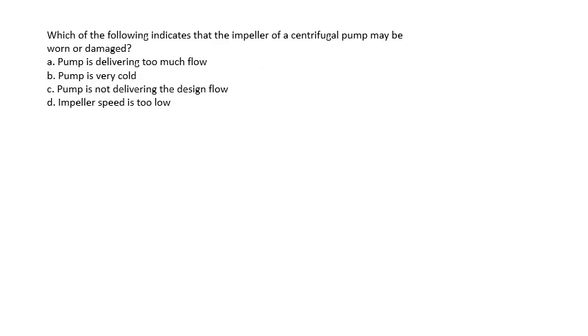Question 9: Which of the following indicates that the impeller of a centrifugal pump may be worn or damaged? The pump is delivering too much flow, the pump is very cold, the pump is not delivering the design flow, or the impeller speed is too low. The answer is the pump is not delivering the design flow.